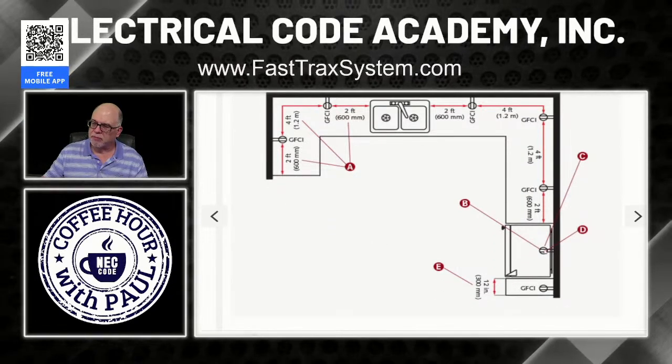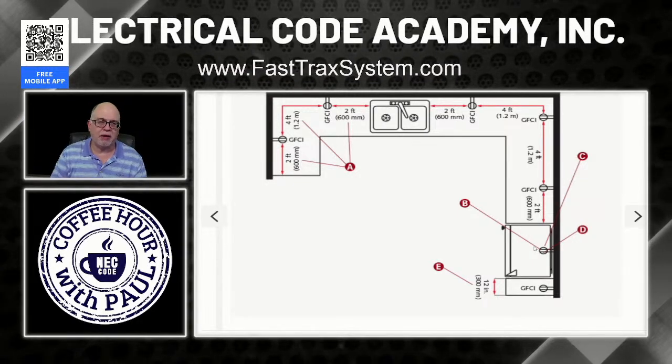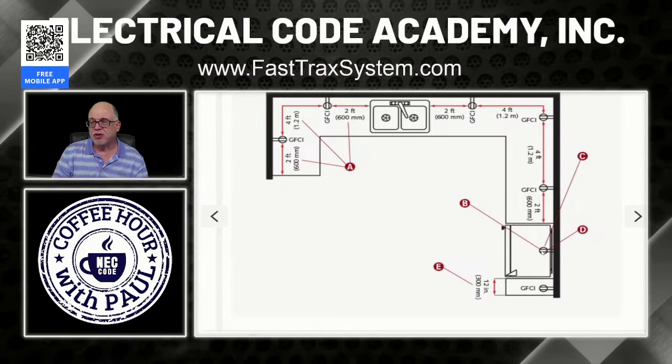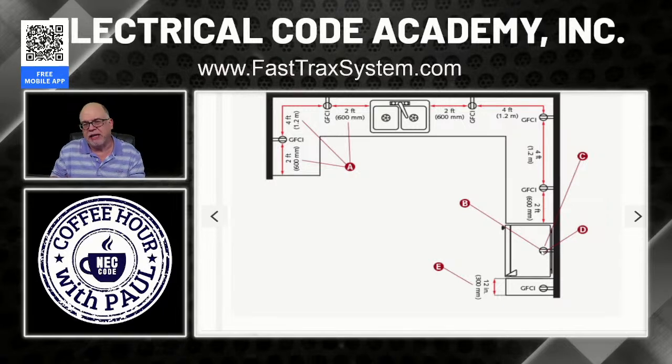Now, notice this receptacle here that's serving the refrigerator. Typically, that is also required to be on the small appliance branch circuit. But as you saw earlier, there is an exception that says this receptacle could be 15 amps or greater, and it could be an individual branch circuit. It doesn't have to be on the small appliance, but the rules in the code act like it's supposed to be, and then it gives you the exception to bring an individual branch circuit to it if you want to, and that's fine.